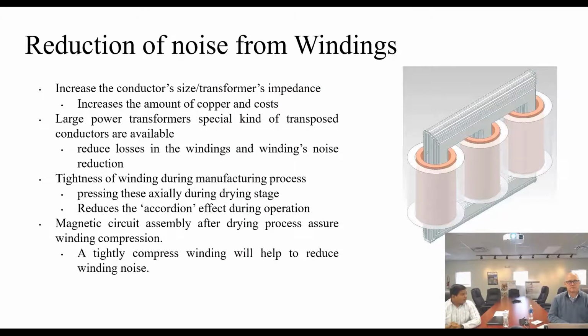So as we discussed the core, the second part that comes after the core is the winding. And winding also plays a role in transformer noise generation. So let's talk about reducing the noise from the winding. Winding noise reduction is achieved by increasing the conductor size or increasing the transformer's impedance. This, however, will increase the amount of copper used in the transformer, and that will affect the cost of the transformer. The other way of doing it, mainly used in large power transformers, is that special transposed conductors are used to make the windings. Those conductors help us reduce the losses of the transformer, and also help reduce the winding noise.